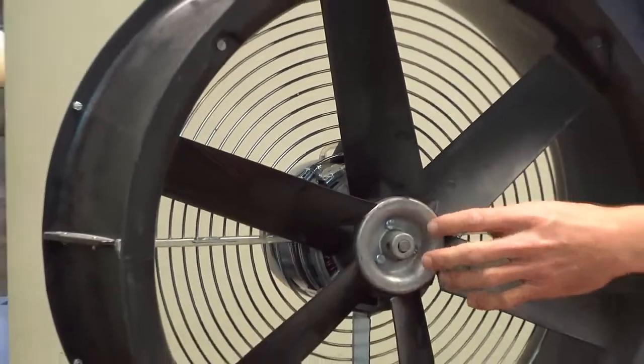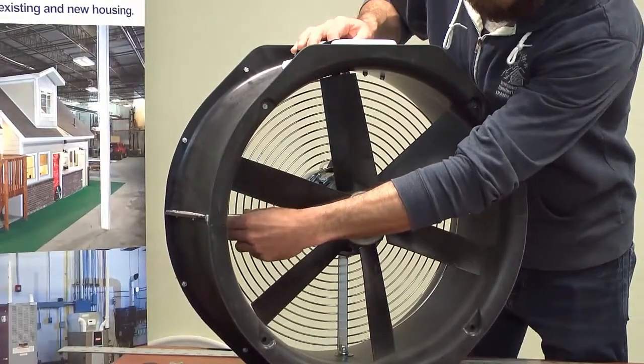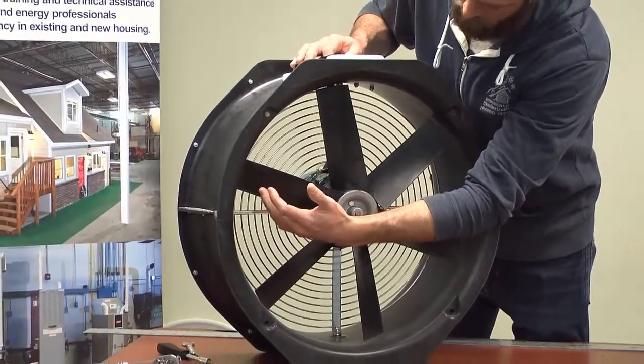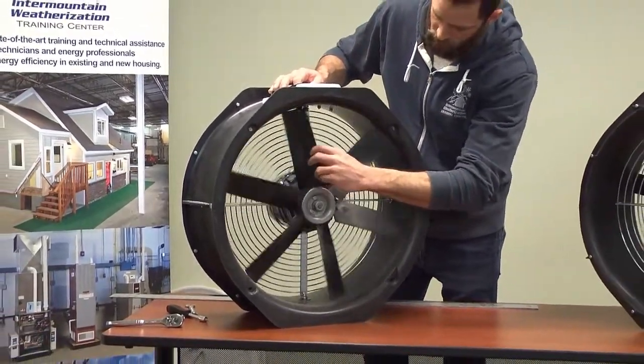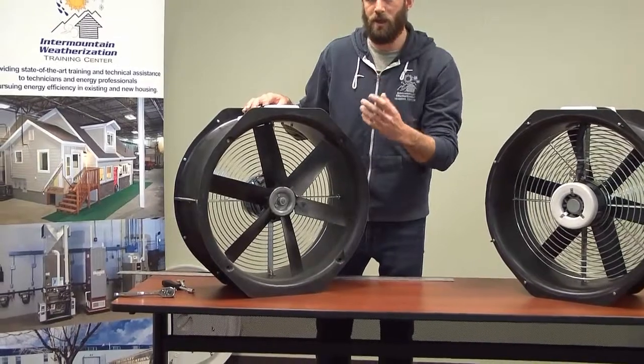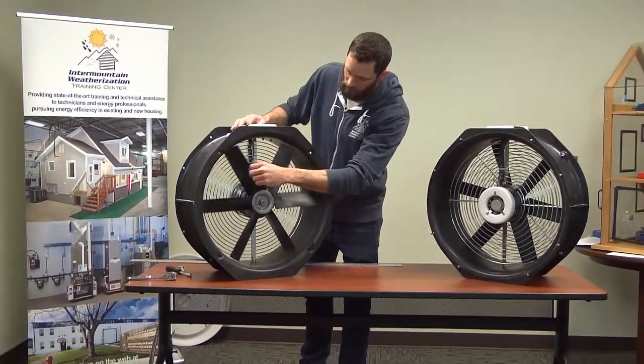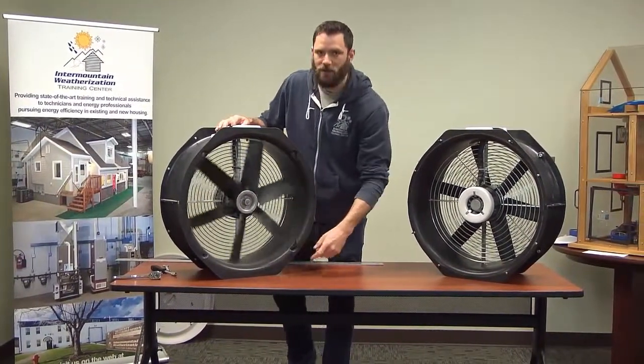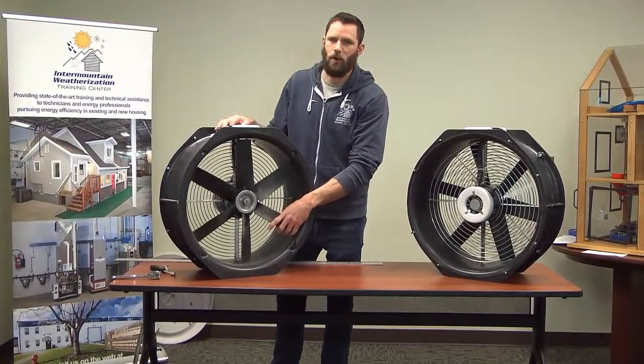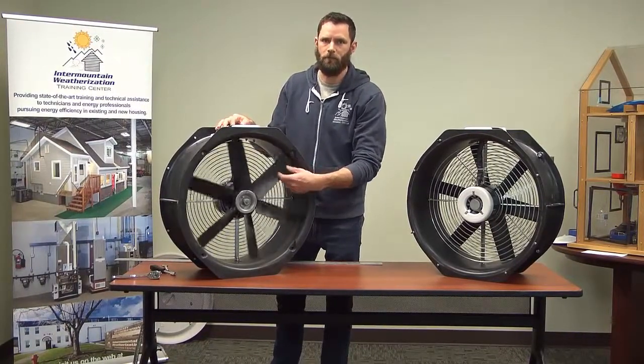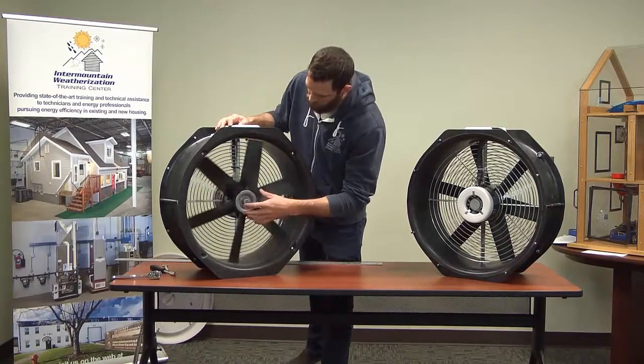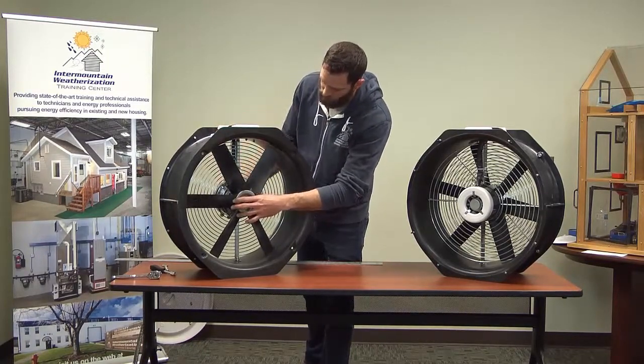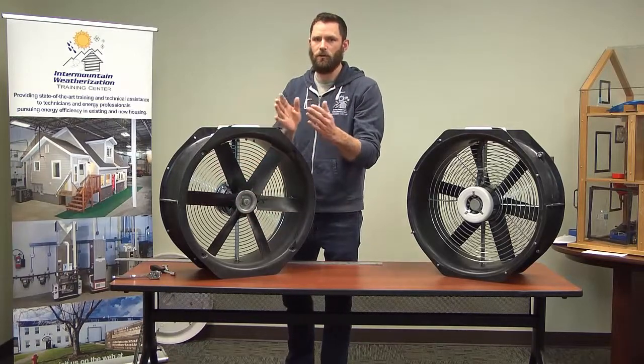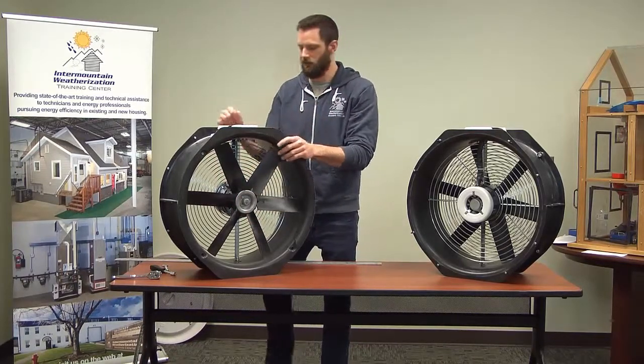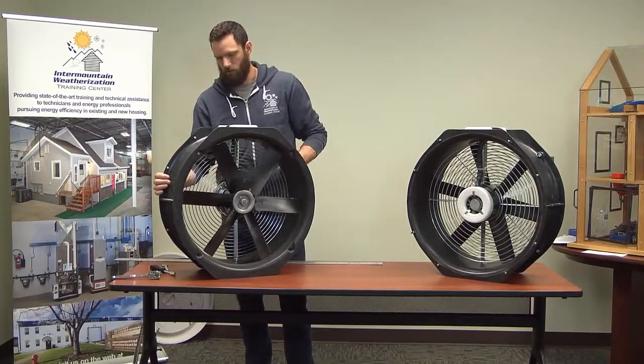Aside from that, if you notice there's some extensive damage, as far as the motor mount is bent, there's something broken, your fan blades are rubbing on the housing, something like that, you're going to want to send your blower door in or contact the Energy Conservatory, because that's a little more extensive than what you want to get into. But if you just need to slightly move the motor in or out to meet that standard, then you can just by doing that. So.